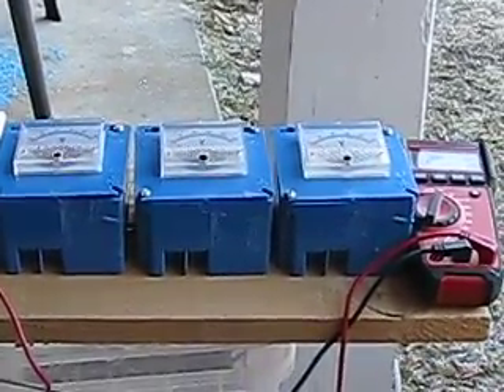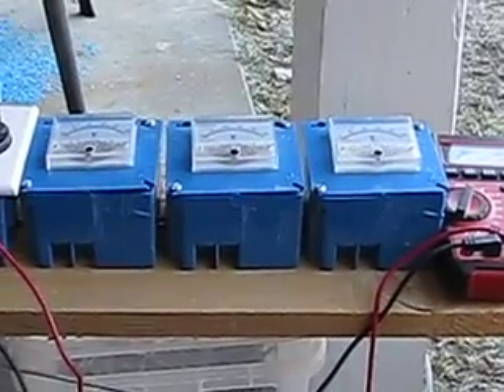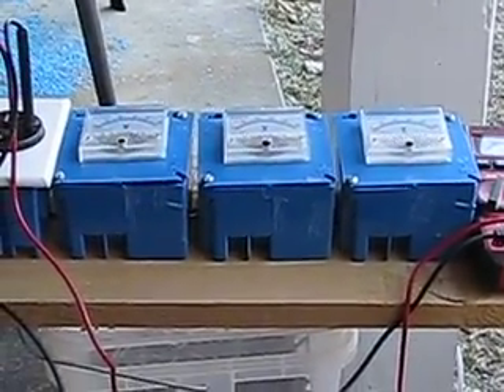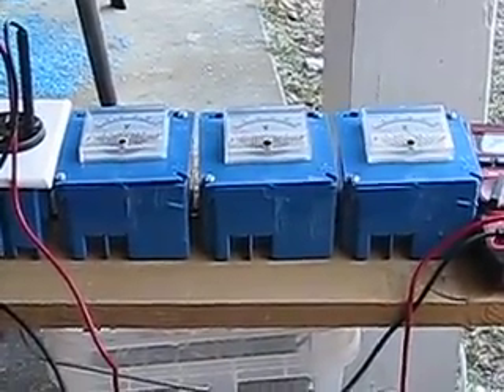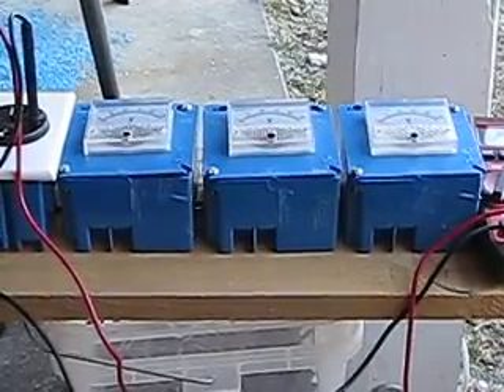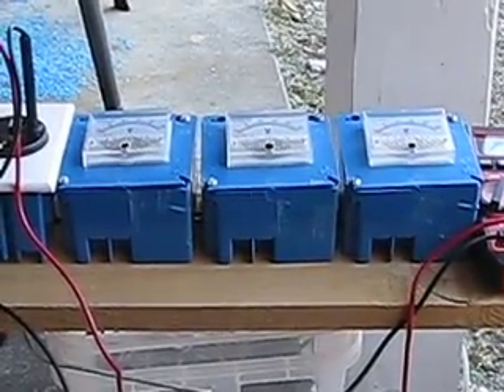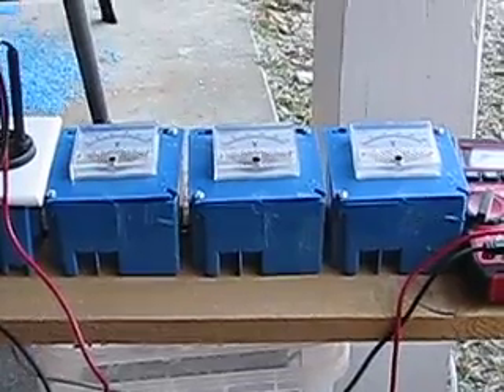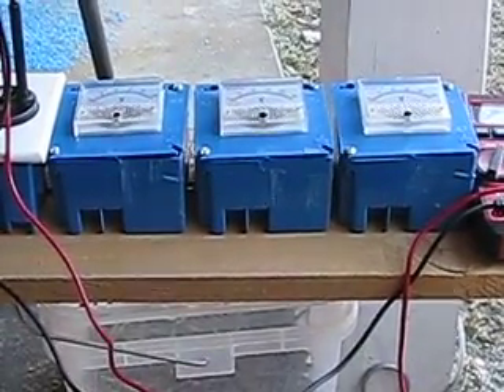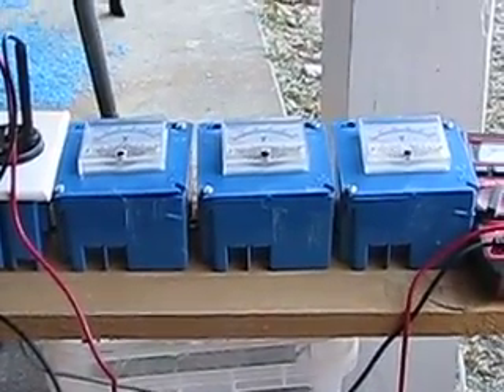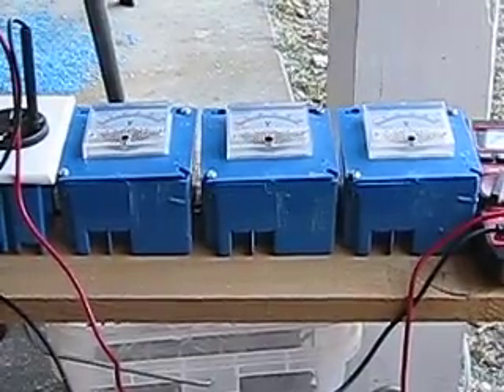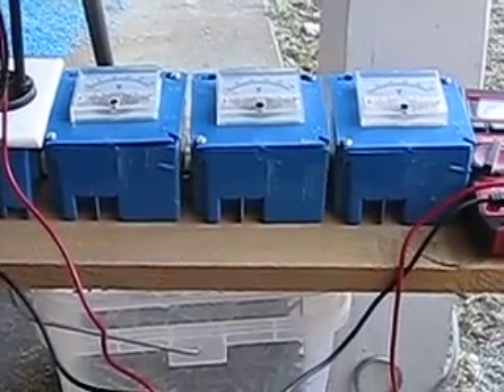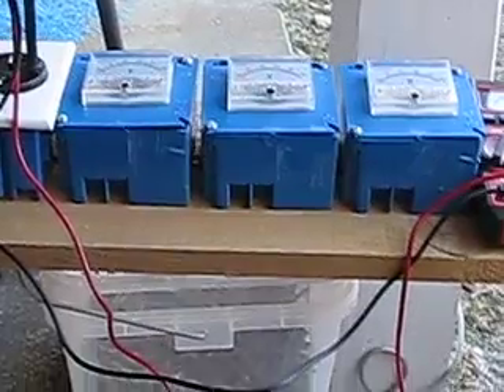Checking the power with the meter, I determined that one leg was about 94 volts, the other leg was about 115 or so, which is fine. The 220 line was probably close enough to 220. So it was probably that 94 volts that was having an issue with some things in the house.